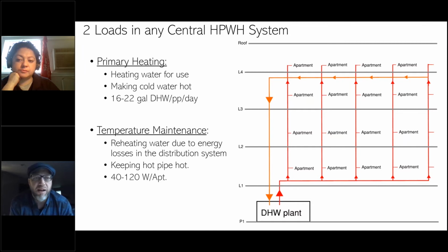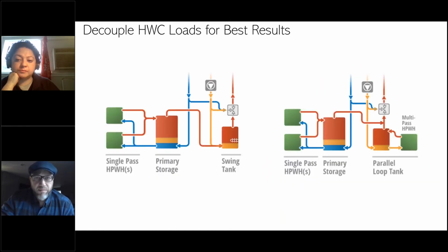There's both the heat plant and the distribution system, and there's a lot happening right now around the distribution systems and how to really squeeze the losses out of them. So I showed you the two loads, and the advice I would give is you'll get the best results if you decouple the hot water circ loads from your primary heating. There's a lot of reasons for that. This doesn't mean it won't work, but I'm recommending that you decouple it in some way, shape, or form.